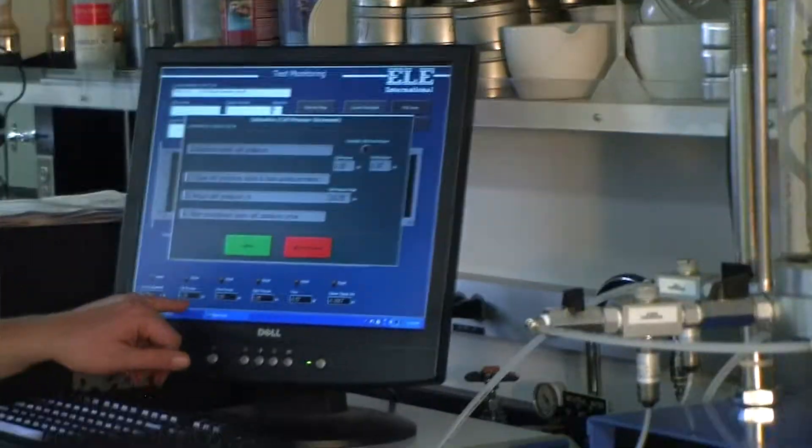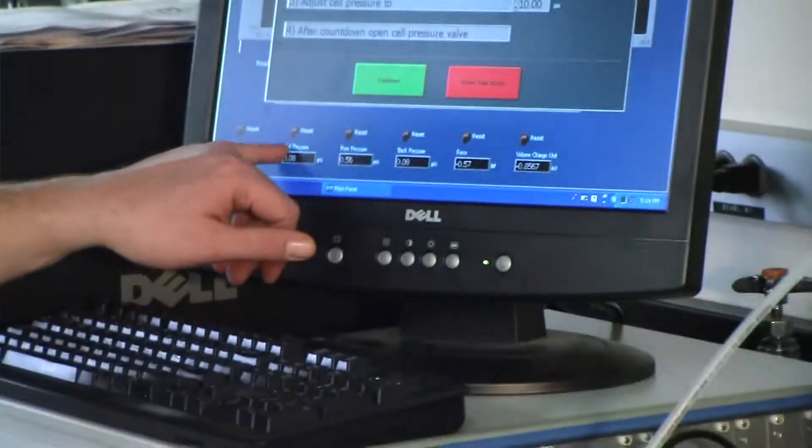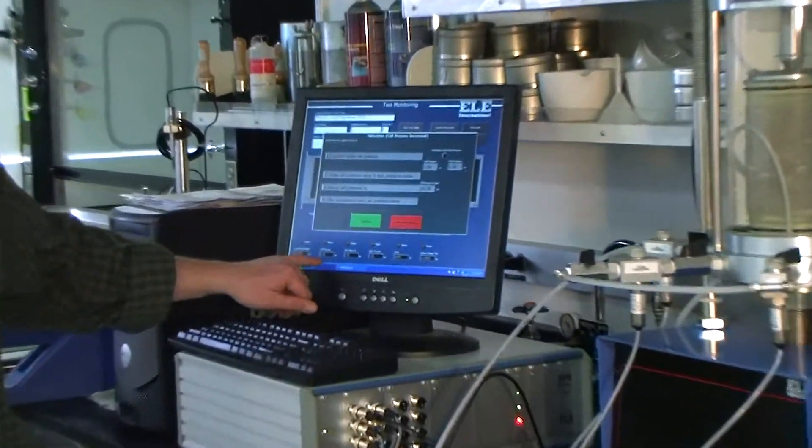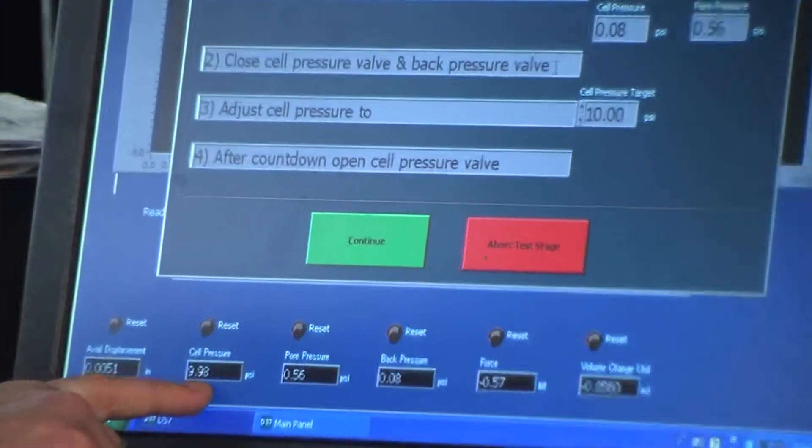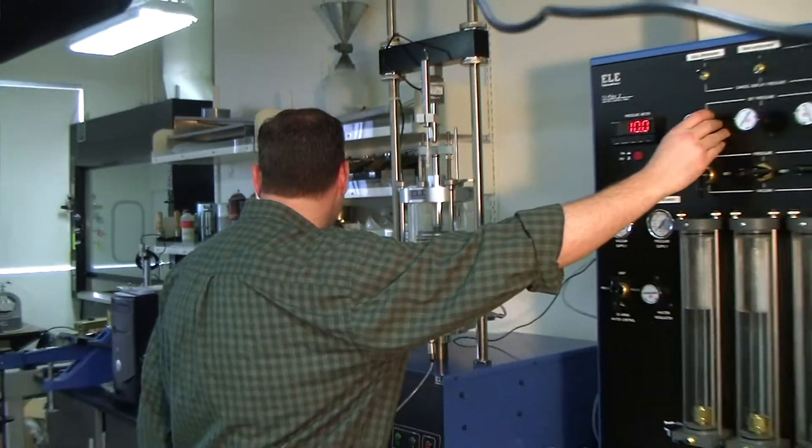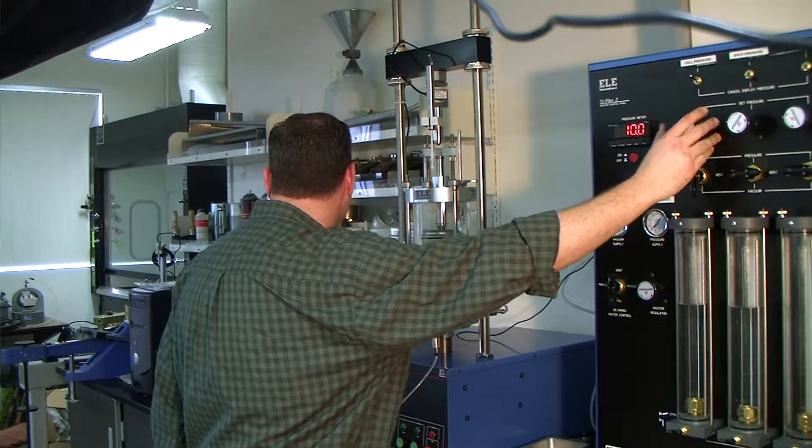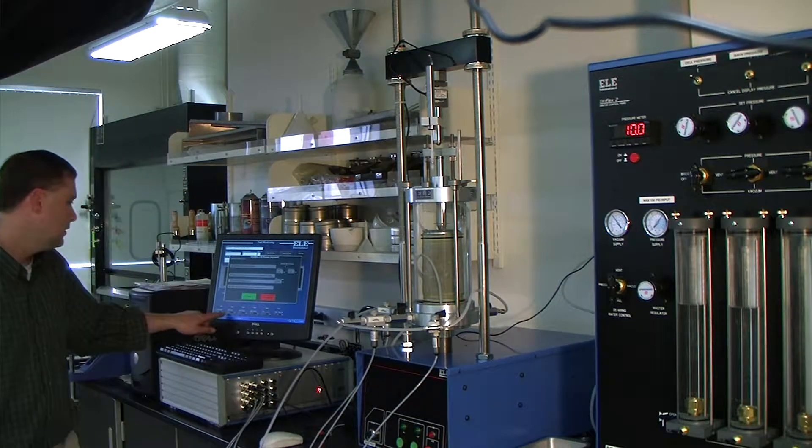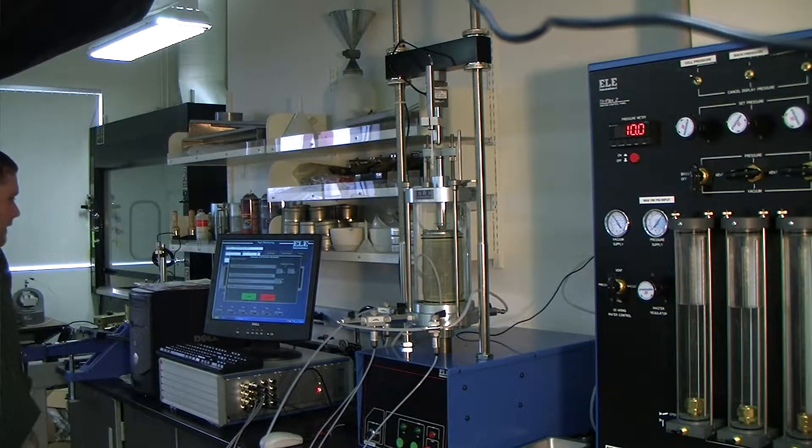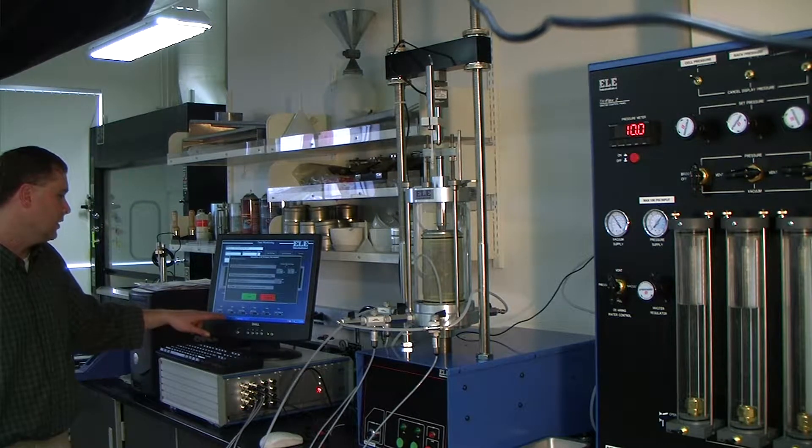Look and see what the value on the screen is saying. If you notice, the value on the screen hasn't changed because I didn't change the valve to pressure. Now that I have, it's saying 9.98 PSI. That's pretty close to 10. You want to do some fine adjustments to make sure you're right at 10 or very close. Being a little above 10 is okay in this case.